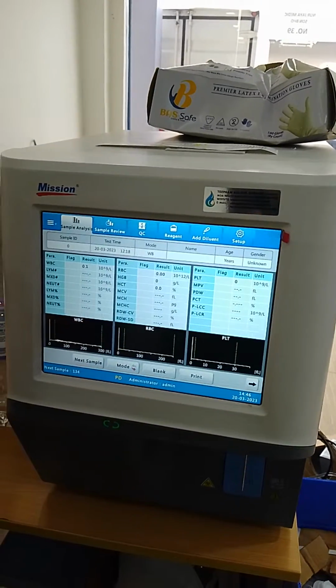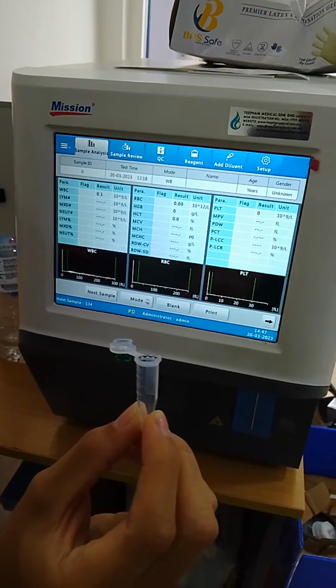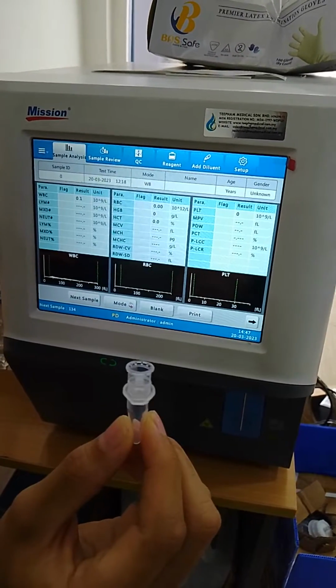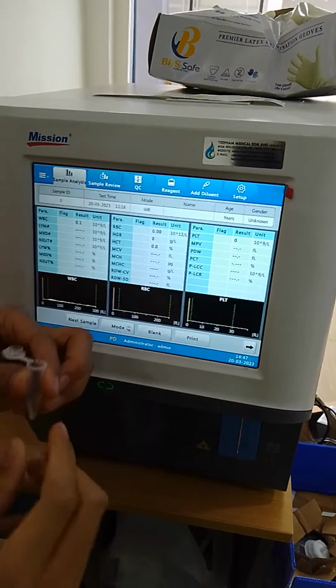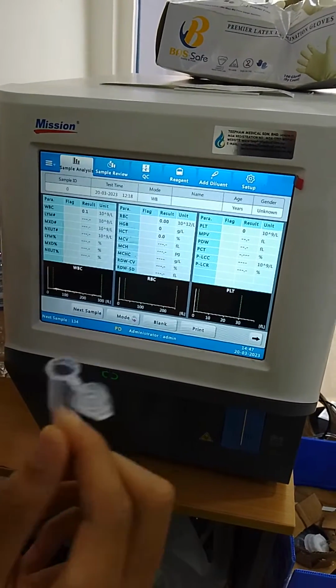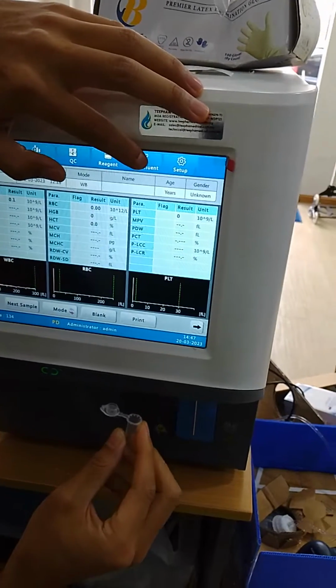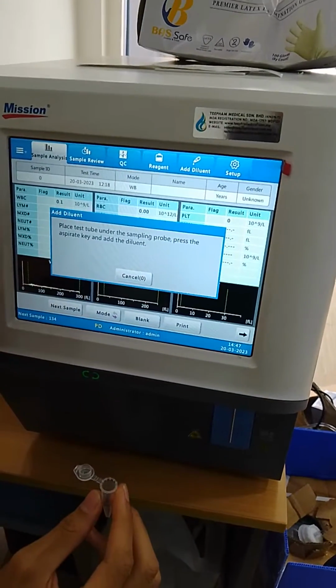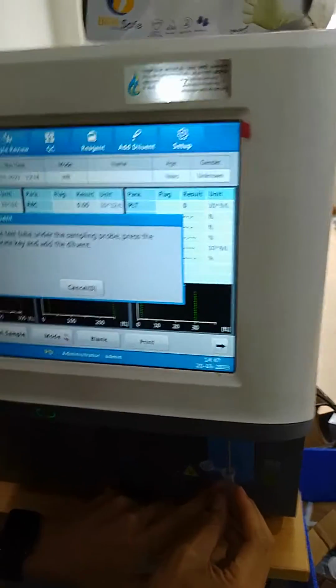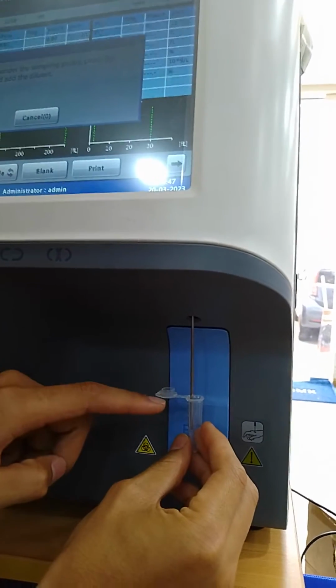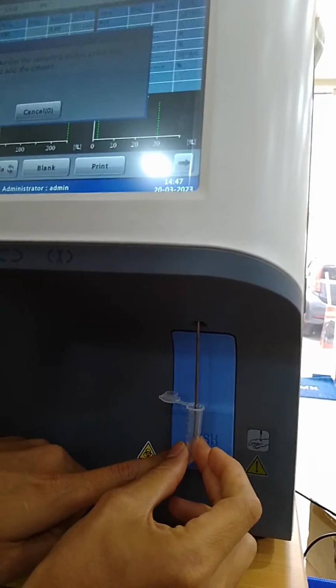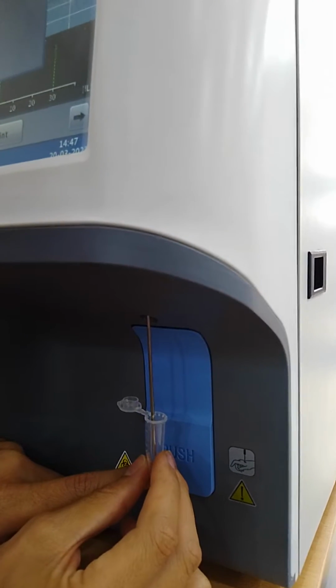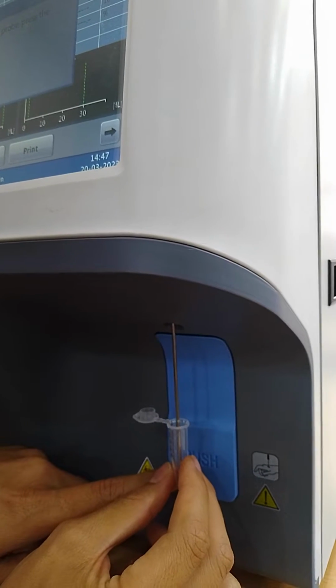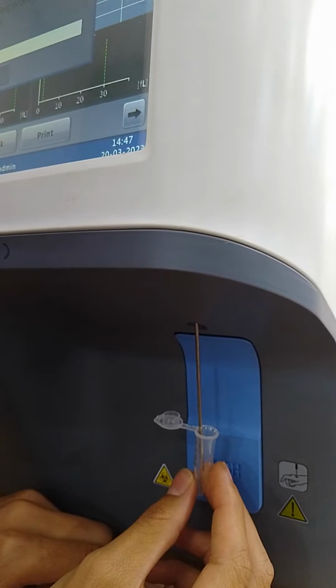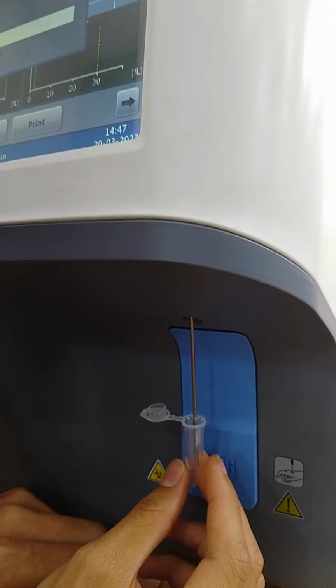Okay, first you need to take the centrifuge micro tube. Okay, in PD mode you have to add some reagents in this tube. So you need to press add diluent, and then this message comes out. And then what you can do is you put in the tube. Make sure the sampling probe is put inside the tube, and then you need to push the aspirate key here until all the reagent is put into the tube. Wait for several seconds.